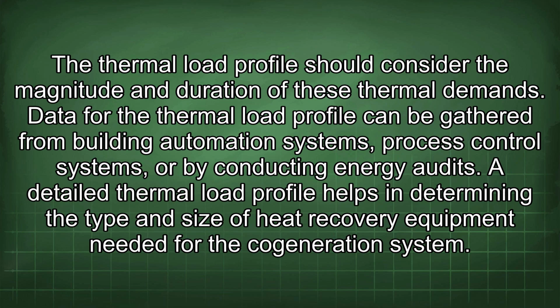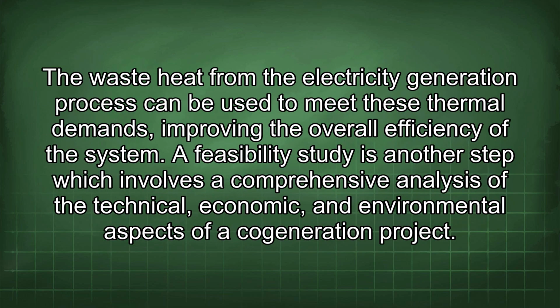Data for the thermal load profile can be gathered from building automation systems, process control systems, or by conducting energy audits. A detailed thermal load profile helps in determining the type and size of heat recovery equipment needed for the cogeneration system. The waste heat from the electricity generation process can be used to meet these thermal demands, improving the overall efficiency of the system.